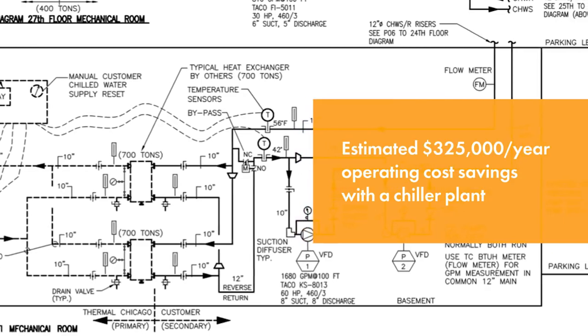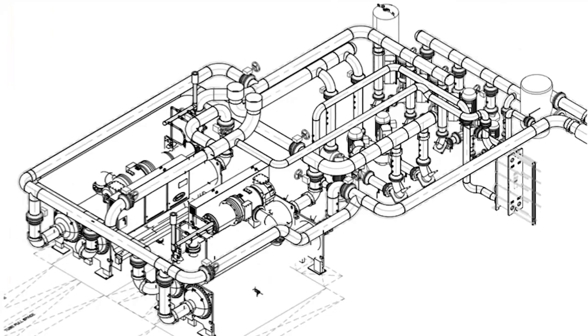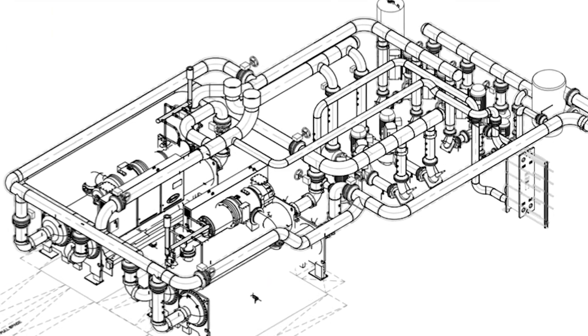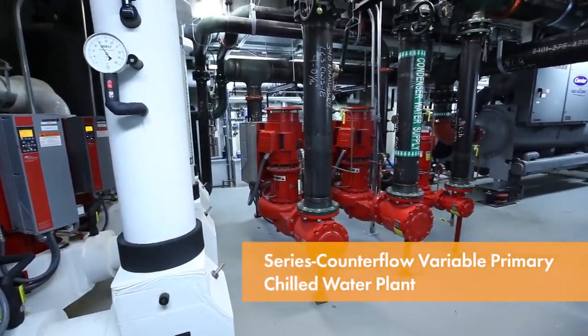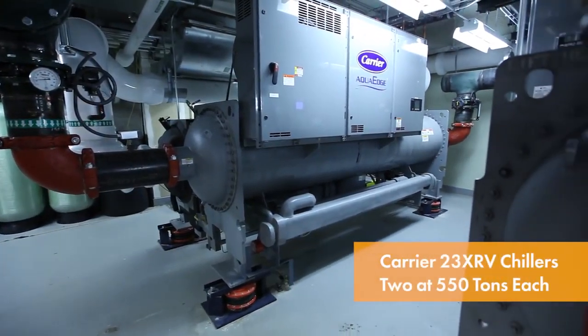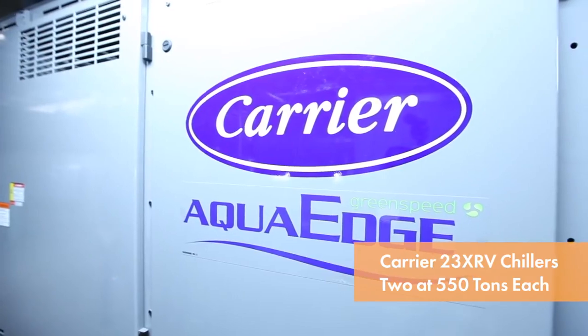They were willing to let us go out and really try to push the boundaries on energy efficiency and design. So we created a series counterflow chilled water plant that had a variable primary chilled water pumping system. This is one of the most efficient configurations of a chiller plant that can be built.